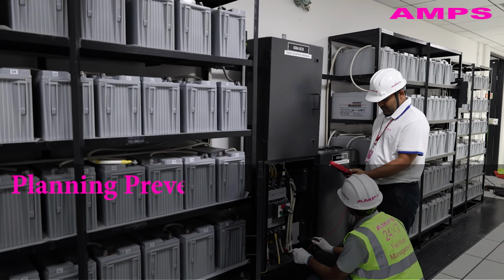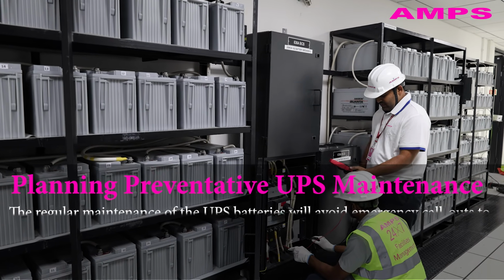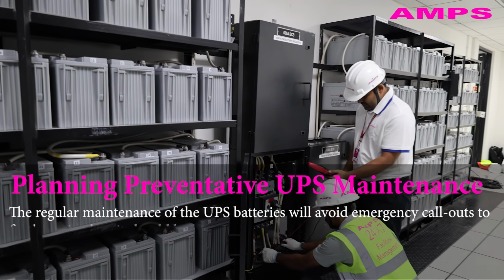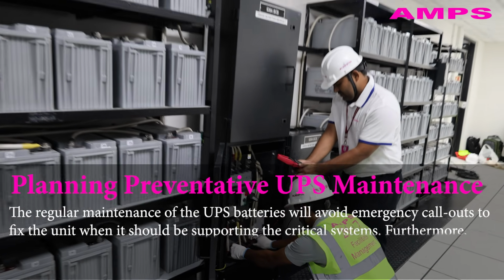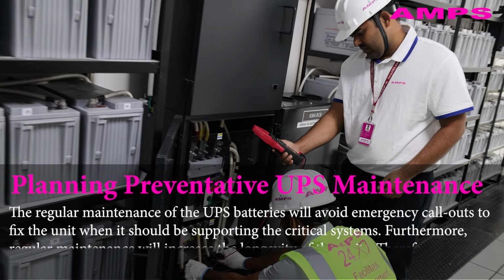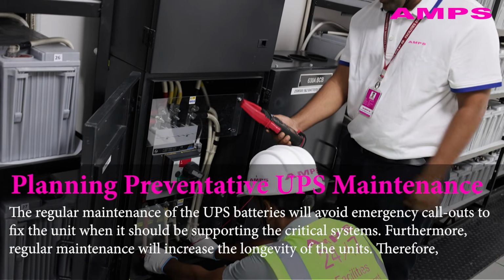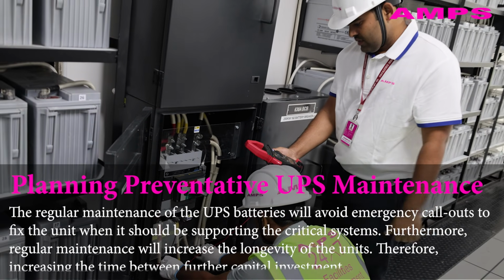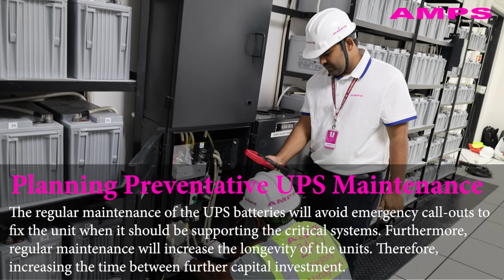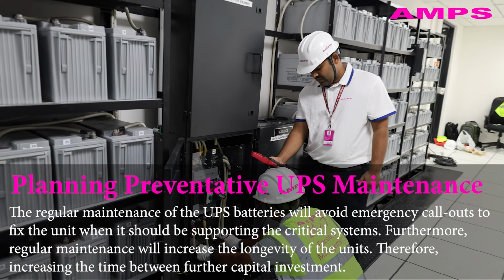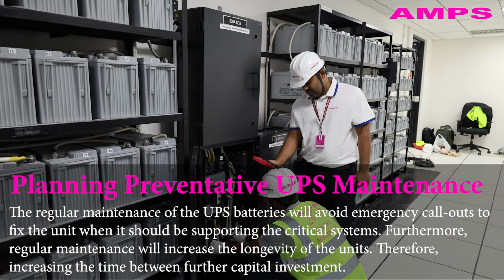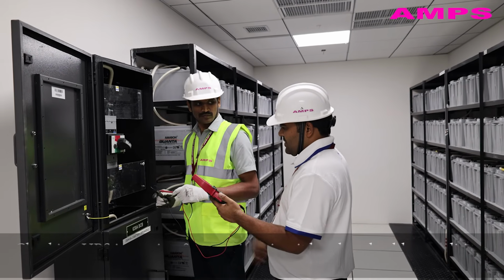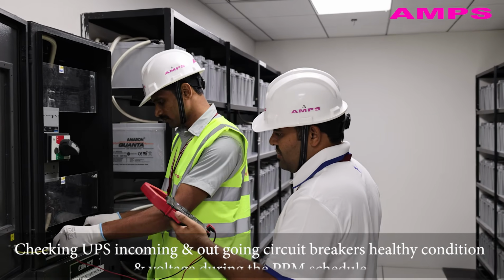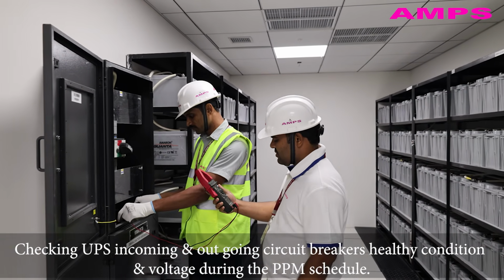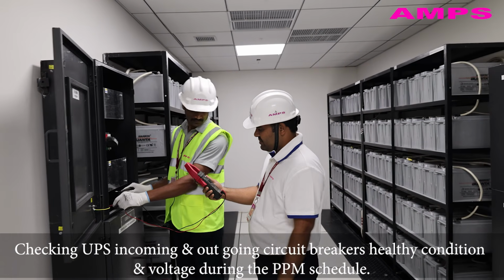Planning preventative UPS maintenance. The regular maintenance of the UPS batteries will avoid emergency callouts to fix the unit when it should be supporting the critical systems. Furthermore, regular maintenance will increase the longevity of the units, therefore increasing the time between further capital investment. Checking UPS incoming and outgoing circuit breakers' healthy condition and voltage during the PPM schedule.